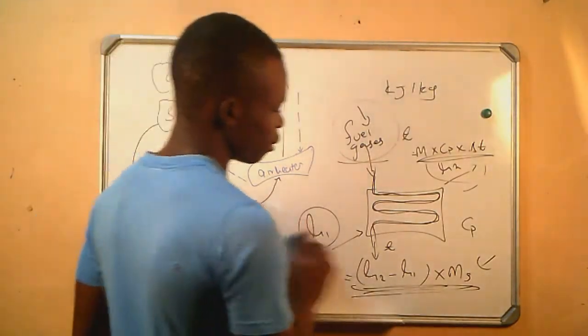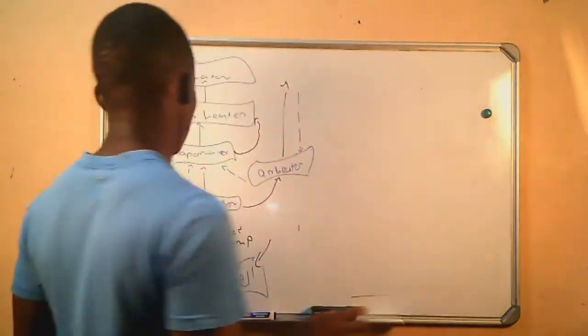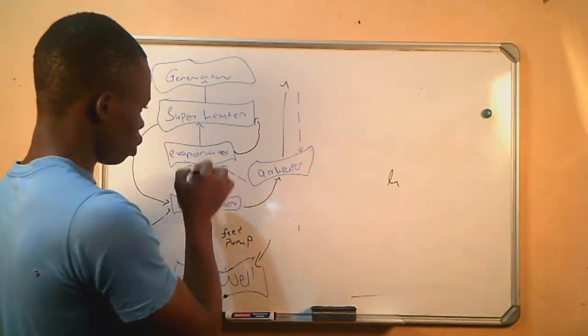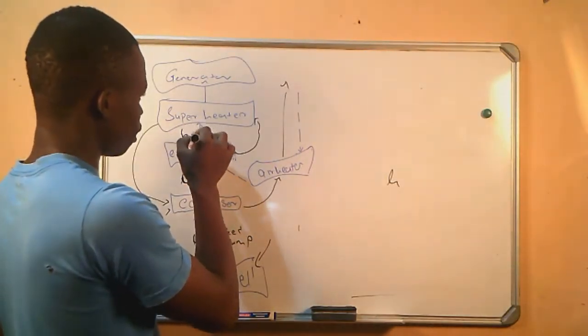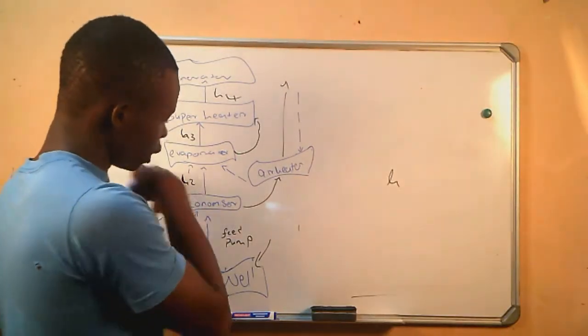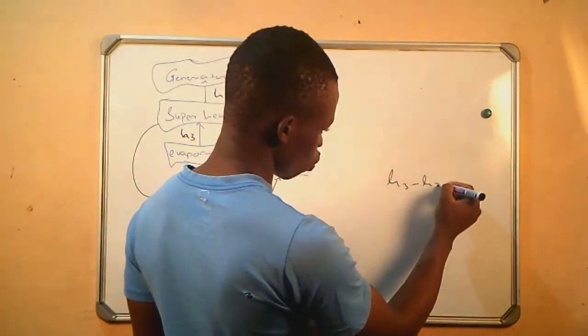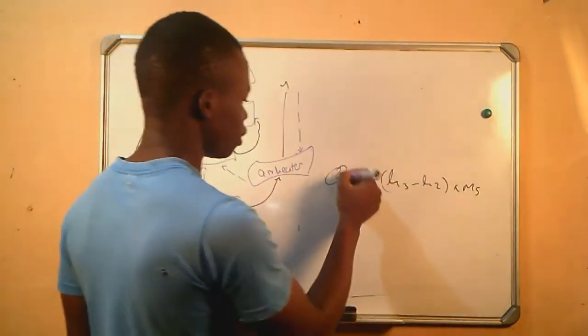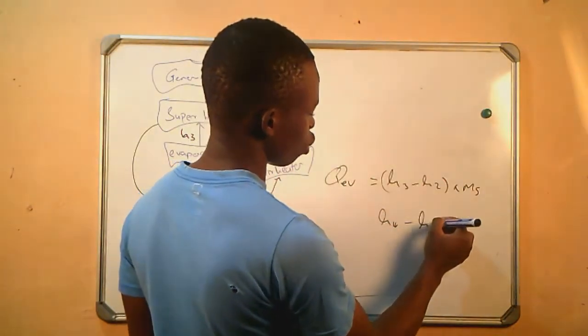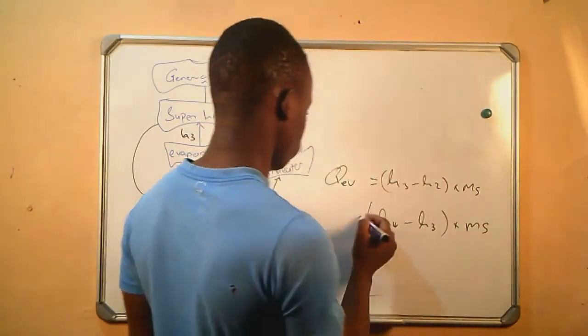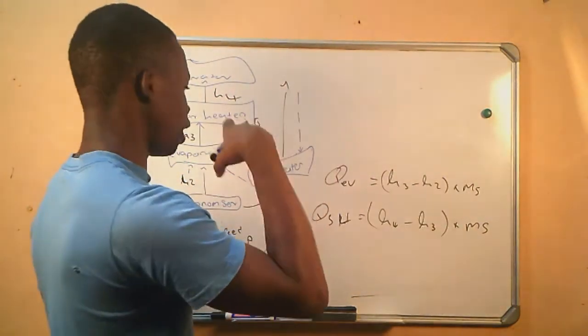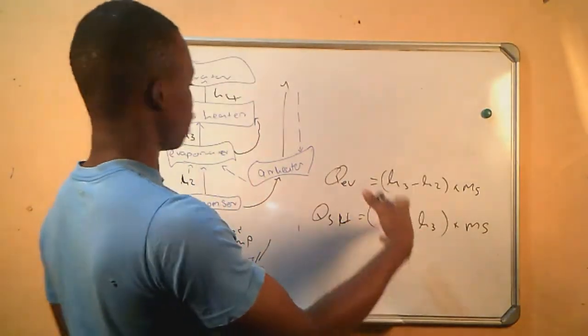The same thing will happen in the evaporator. We know the enthalpy values are H1, H2, H3, and H4. In the economizer it's H2 minus H1. In the evaporator it will be H3 minus H2, times the mass of the steam. This is at the evaporator. And in the superheater it will be H4 minus H3. This is the heat gained or lost at the evaporator, and H4 minus H3 is the heat gained or lost at the superheater.